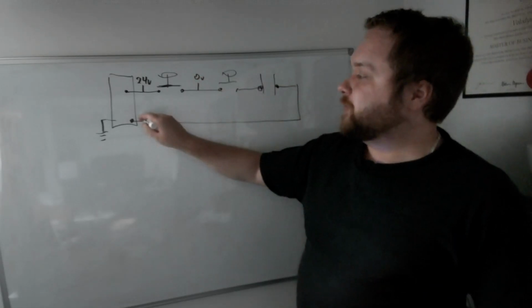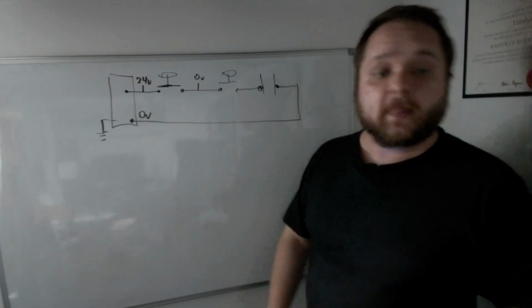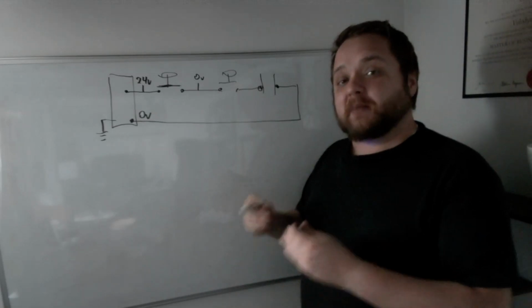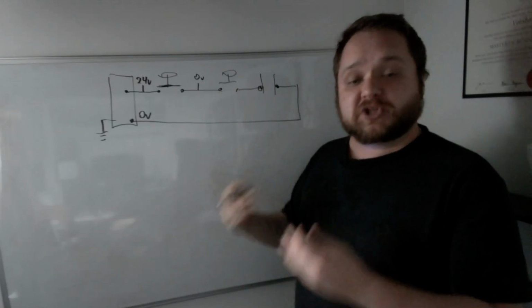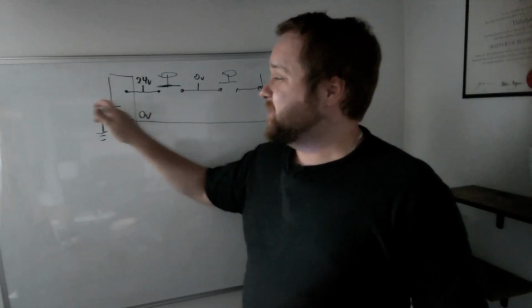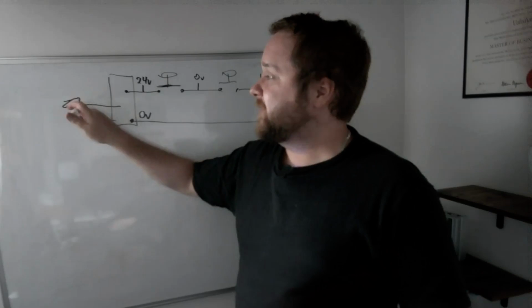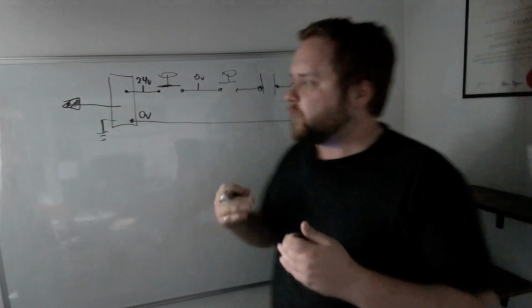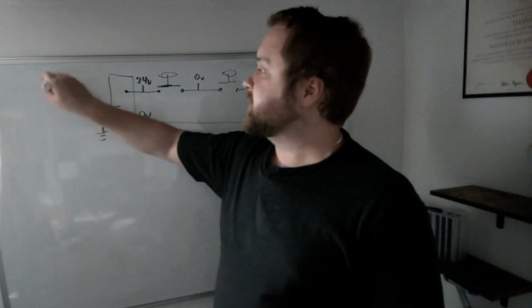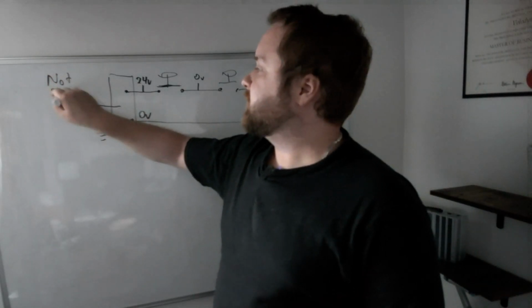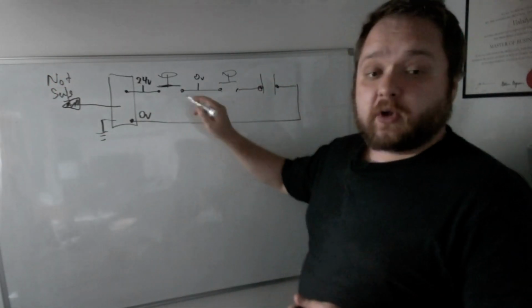Consequently, we have 0 volts here on the first channel, which basically means that the current application is not safe, or the current machine is not safe to operate. That's going to be, again, relayed by the safety relay to other devices within that specific electrical panel or electrical chain, that this is not safe. So here I'm going to say not safe. Once I close all of these elements, right?